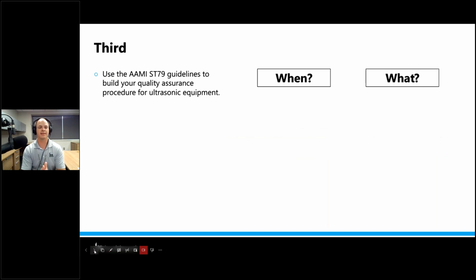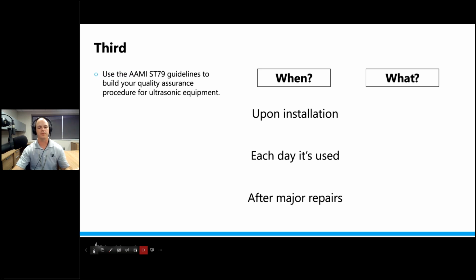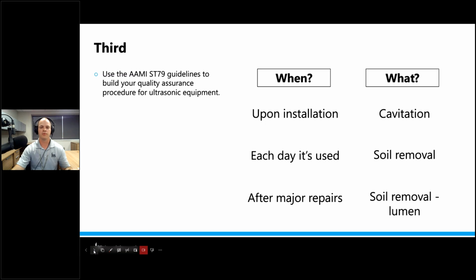Third, you're going to use those ST79 guidelines to build your quality assurance procedure for the ultrasonic equipment. All right. So whatever your daily procedure is, use that ST79 as guidance. You don't have to make these things up on your own. You have guidance there, and that's where you would start. And it's going to tell you about when to do it. You know, we talked about it upon installation. We're going to do it every day that the equipment's in use. And we're going to do it after major repairs. All right. And what are we going to test for? We're going to test for cavitation. We're going to test for soil removal and soil removal within lumens. All right. So that's the kind of configuration that ST79 would recommend.